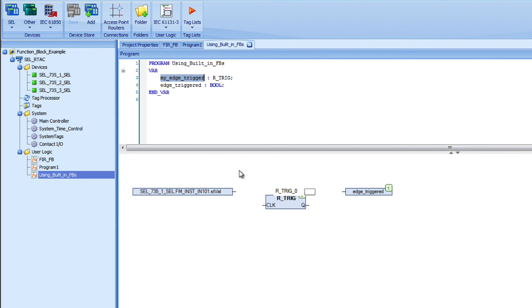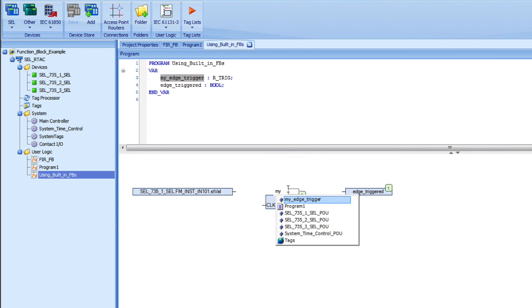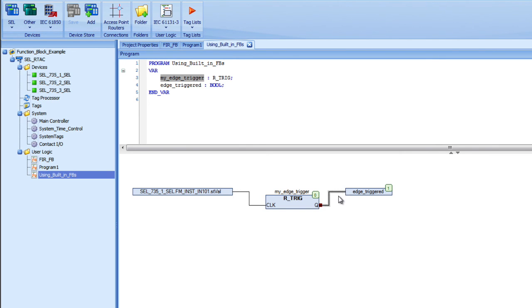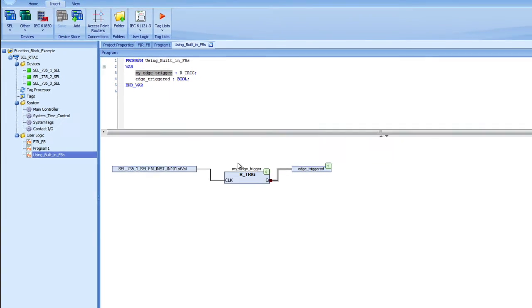To use that, I need to make a function block instance of it, which I did up here in the var section. Similar to the function block that I created, I make instances of that function block in the var section. If I'm using a function block that is a standard function block like an R_trig or a T_on or one of those things, I also have to make instances of those, and I can name them whatever I want.